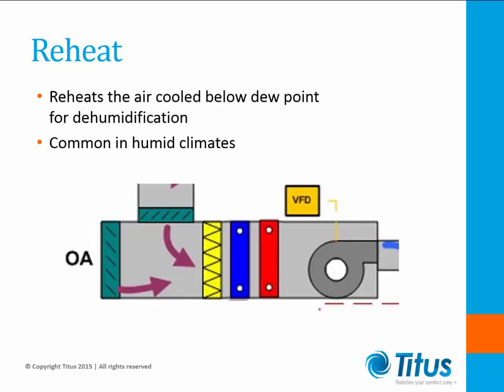The opposite coil configuration is shown with the cooling coil first and the heating coil second. This configuration is known as reheat. The cooling coil subcools the humid air below dew point for dehumidification. Because the air has been cooled so low, a heating coil may be used to bring the air back to a comfortable level. This configuration is typically found in moist, humid climates.